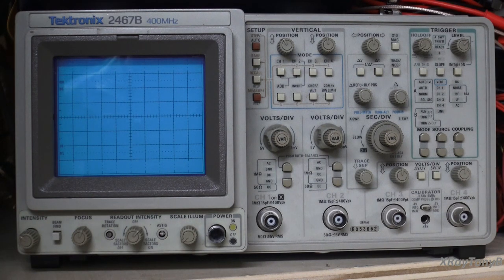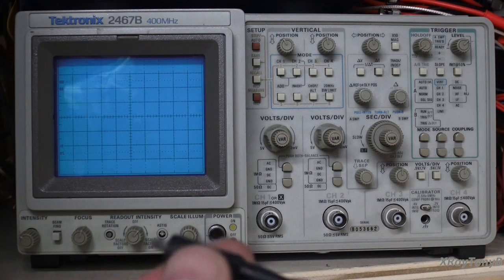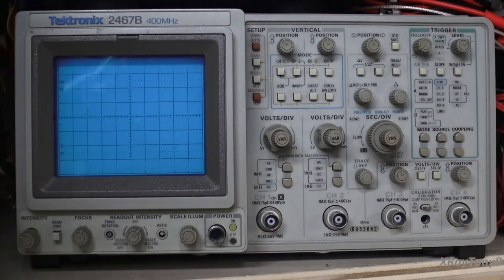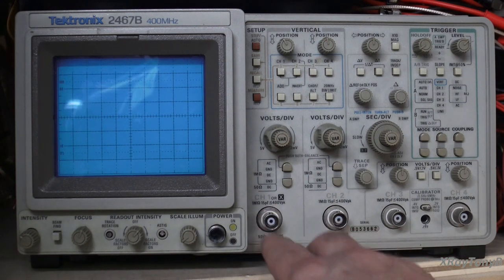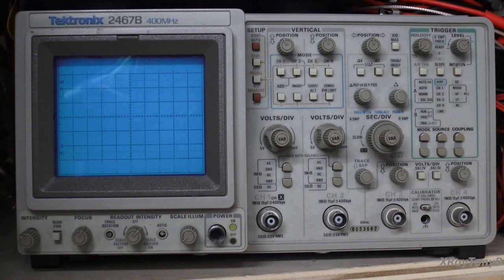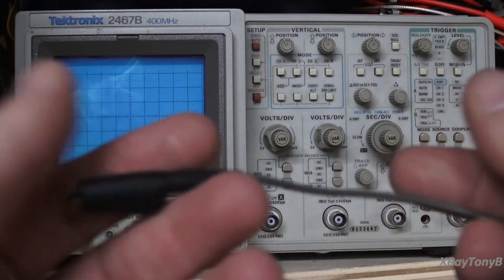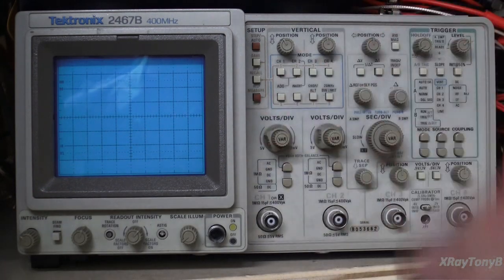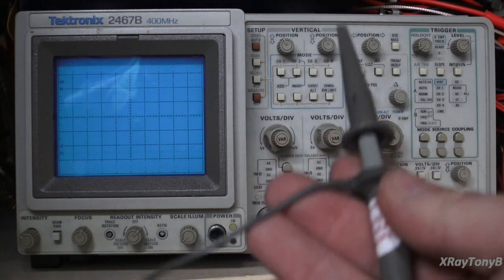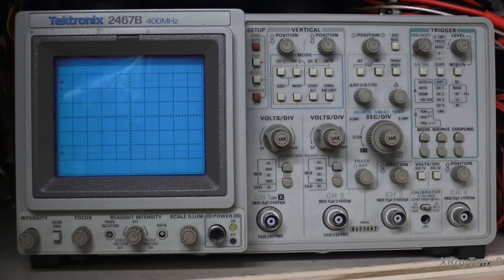That's very important, because what happens if you connect this tip, this ground lead, to something that is not at ground potential with respect to your AC mains ground? You are going to put that voltage onto this ground here. And potentially, you could cause a really bad short, and a couple things can happen. Number one, you can blow this wire apart. I've seen it happen. It'll burn the wire right in half. It'll just vaporize. Number two, you can cause damage to the scope. Number three, you're holding this probe, so that voltage can now go into you and cause damage to you.